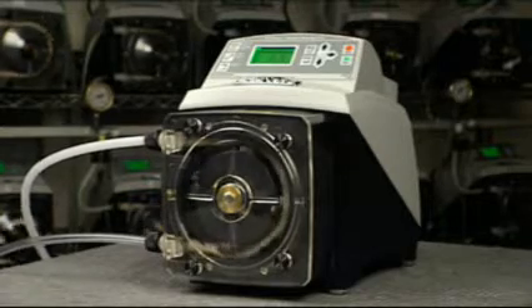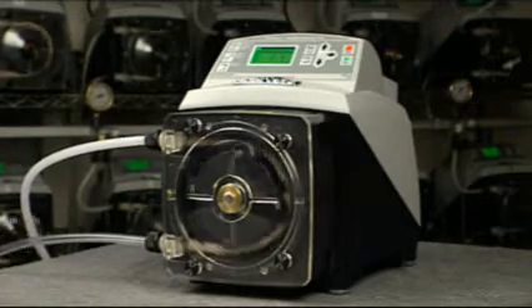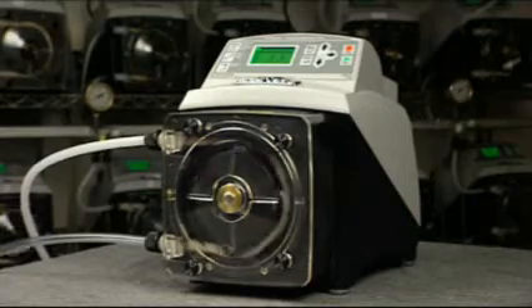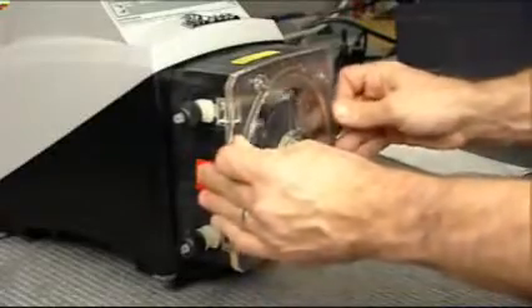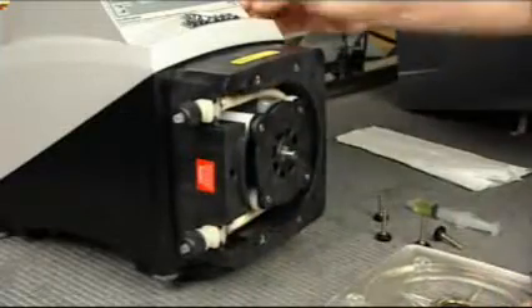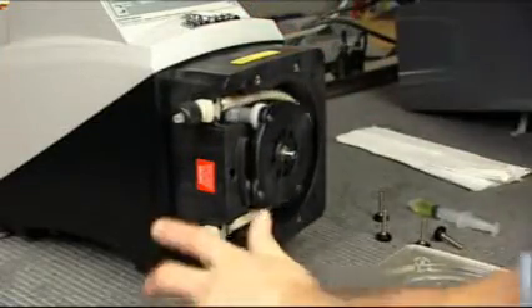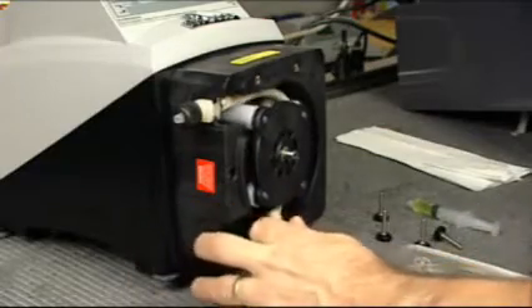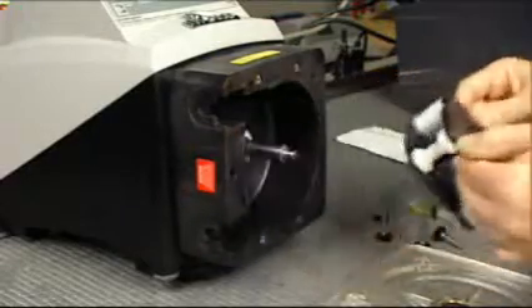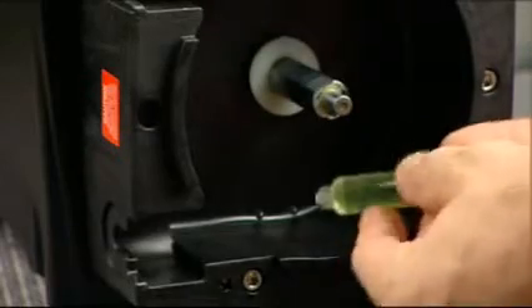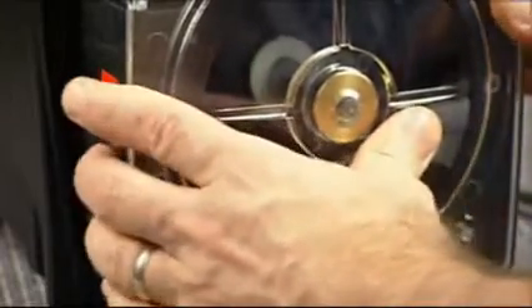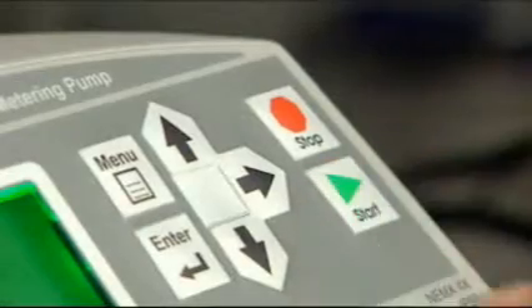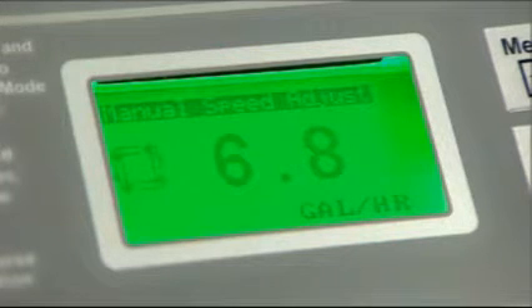While the system is designed to react to most chemicals, the user should perform a test with their specific chemical to ensure proper function. To test the system, remove the pump tube and roller assembly, exposing the TFD sensors. Place a small amount of the chemical inside the bottom of the pump head to simulate a leak. Replace the pump head cover and start the pump. The TFD system should activate within 2 seconds.